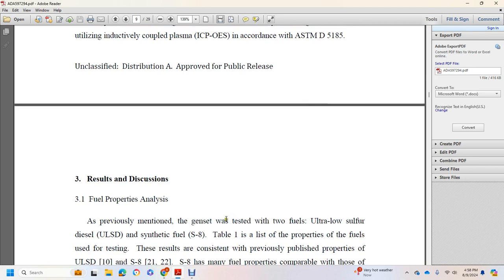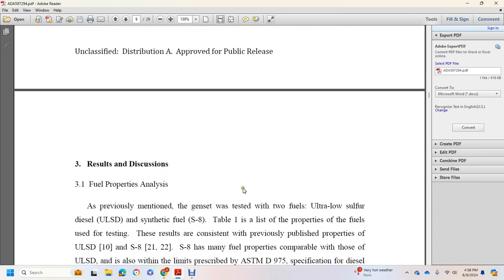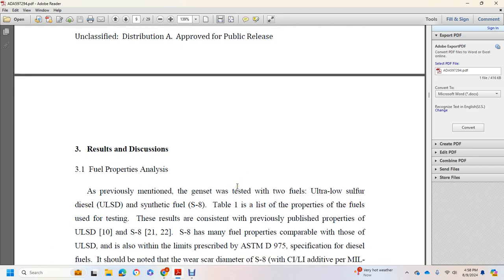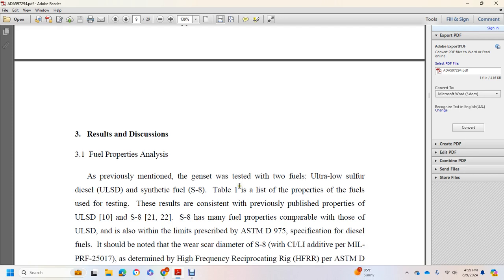3.1. Fuel property analysis. The previously mentioned generator set was tested with two fuels, ultra-low sulfur diesel and synthetic fuel S8. Table 1 shows the properties for the fuels used for the testing, and the results are consistent with previously published properties for ultra-low sulfur diesel and S8. S8 has many properties comparable to ultra-low sulfur diesel. It also meets the limits prescribed by the ASTM D975 specification.